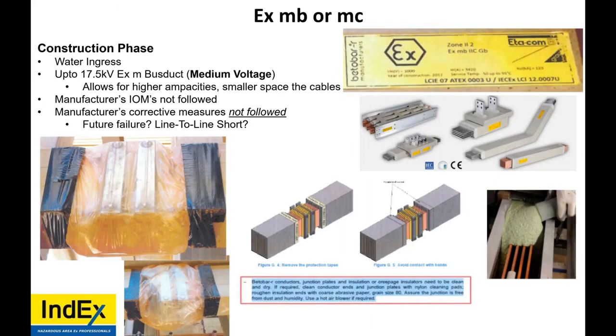Now, here's an example of Ex m connections. This is a modular bus duct that can go all the way up to 17.5 kV, 17,500 volts. These are used as a replacement for cables because they allow for higher current and higher voltage in a smaller space without the use of cables. It's a wonderful design, but you have to preserve it.